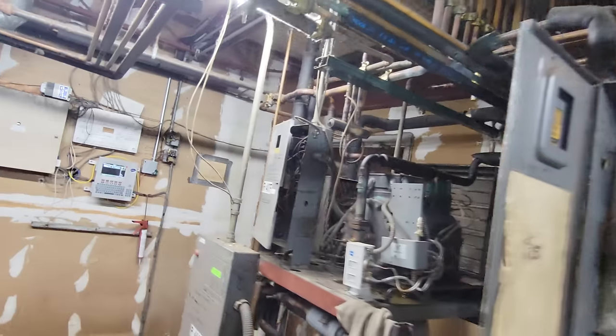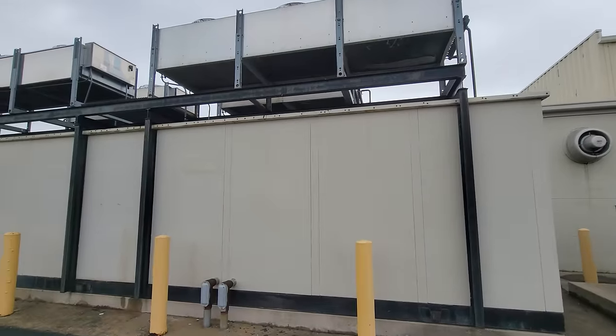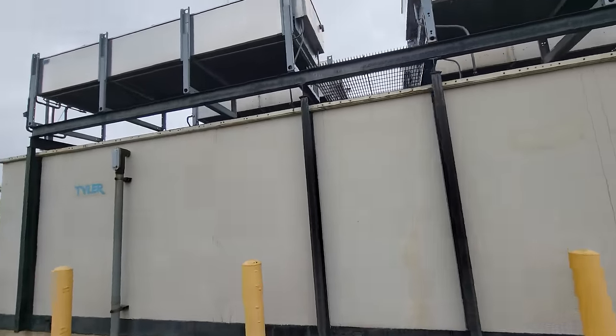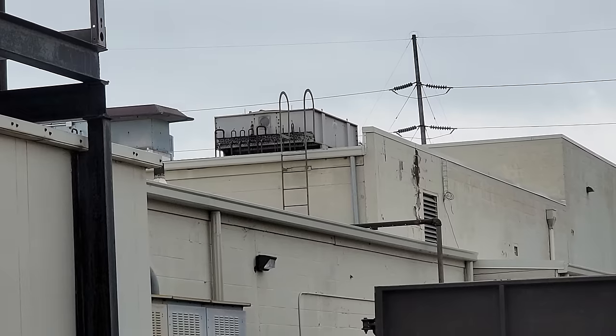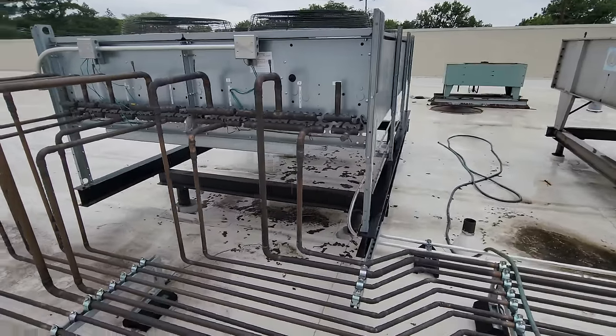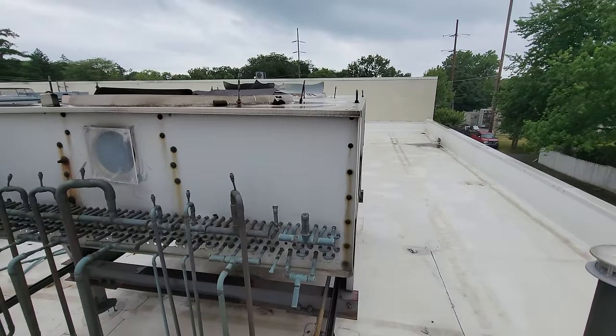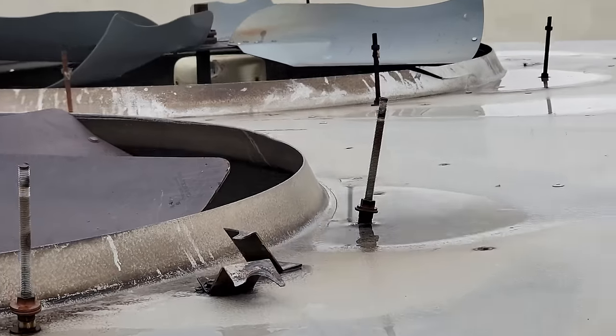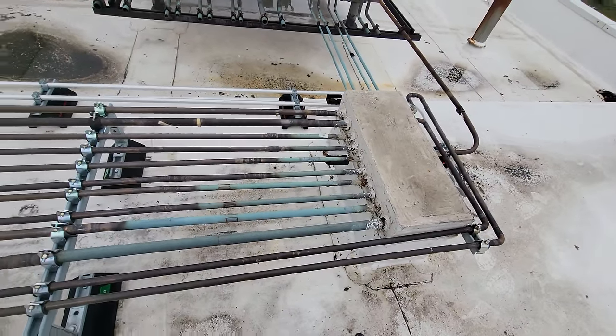We've got to figure out where this condenser is at. I think this one is on the roof. Got to go down there and get it disarmed otherwise it's going to set the alarm off. That's the other rack and the tile house there — I thought maybe it was on that one, but it's not. The one we're going to be working on is way up there — that's the roof access area we need to get up on. This has a newer condenser on it. As you can see, we've got multiple different circuits which are actually labeled, which is kind of nice. The other one was a death trap — it had blades out the top that would about fling off and take your head. Let's see if we can find this leak.